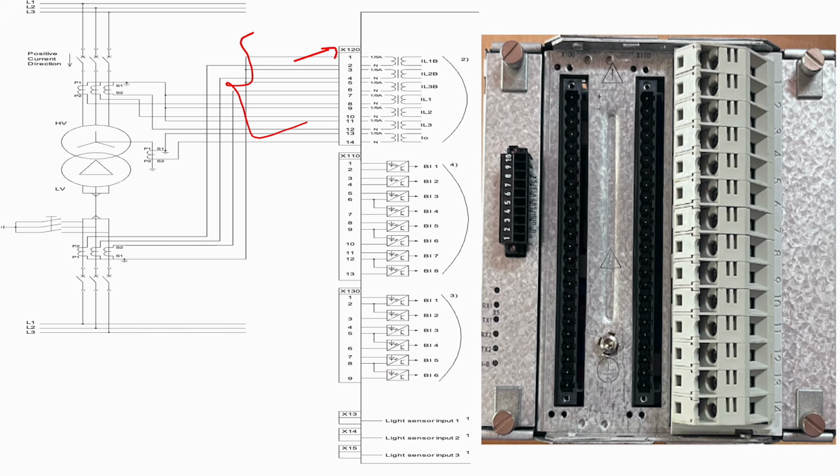up to 14. Here you can see we can connect this relay with 5 ampere CT as well as 1 ampere CT. Okay, the connections remain the same. We just need to select at the time of settings. So there are no different connections for 1 ampere and 5 ampere. We can connect both CTs to the same terminal.